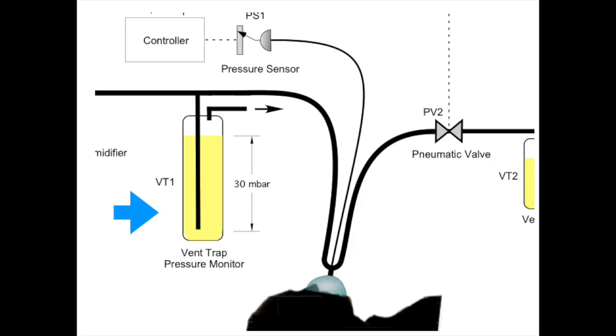The incoming oxygen flow from the humidifier is delivered to the patient outfitted with a non-vented NIV mask. The NIV mask is connected to a breathing system supporting the attachment of two plastic tubes of typical size 22 mm, connecting respectively to the pneumatic valves, and to a smaller plastic tube leading to the pressure sensor.